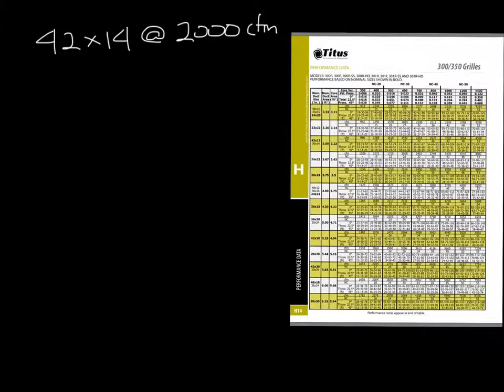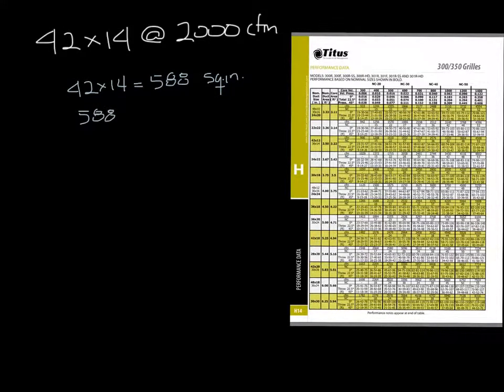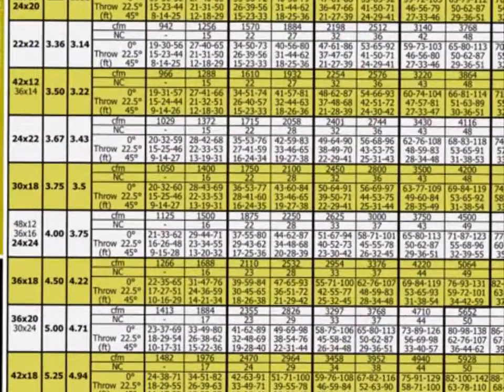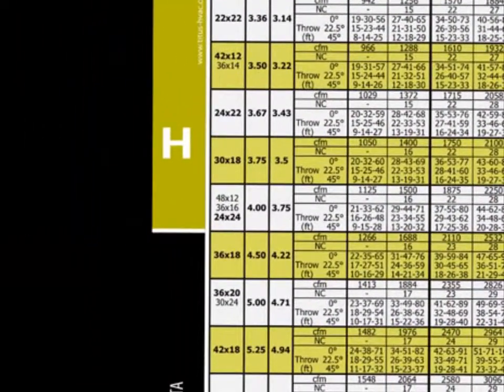Here's what you do to get your data. Multiply the nominal duct height by the width to get the nominal duct area. 42 times 14 is 588 square inches. Divide that by 144 to get 4.08 square feet. Now find a grill that has the closest nominal duct area, which would be this one right here at 4.0 square feet.